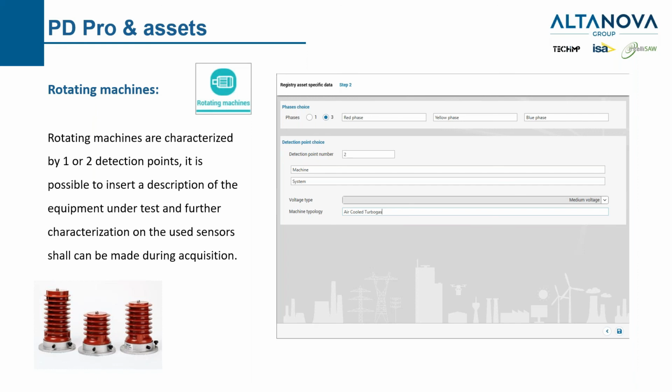synchronization source? This can be useful, for example, if we only have 1 person taking care of partial discharge in our company, but we need many people testing all the plant or all the plants. Those can be also far from each other. In this case, the only expert that is able to analyze the data will have all the information that is normally required to do a proper analysis, the kind of sensor, the synchronization source, and he can, let's say, close many of the doubts that he can have during the analysis of PD.